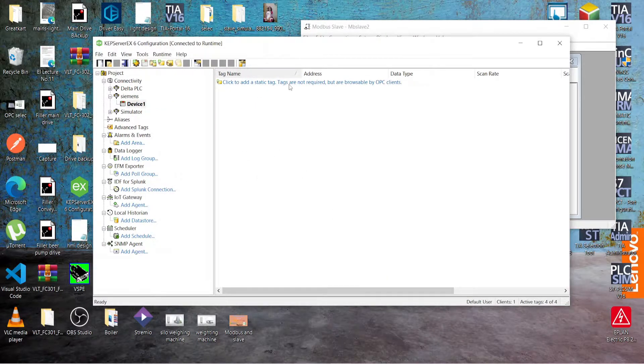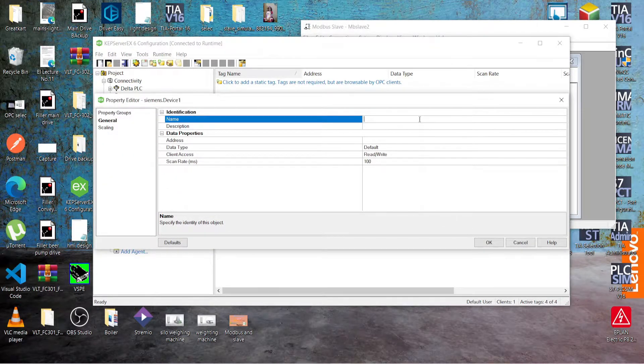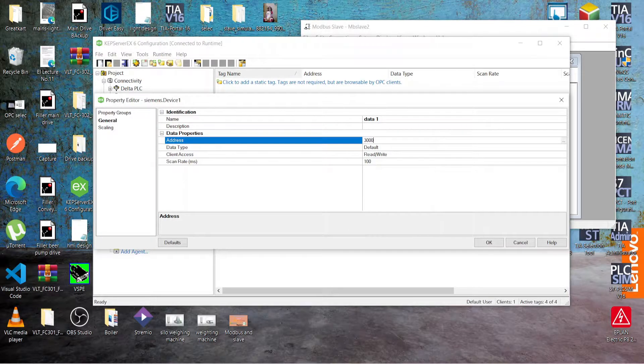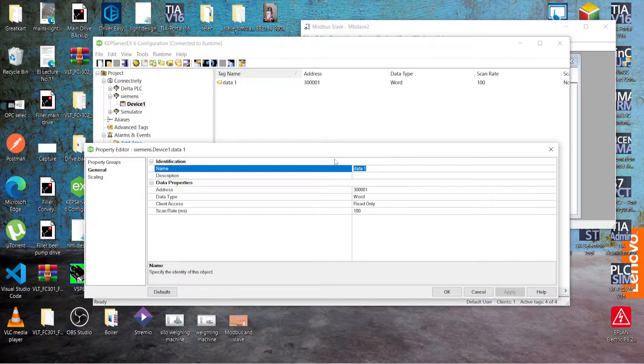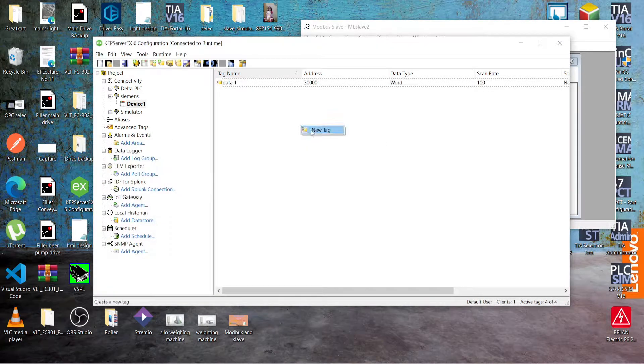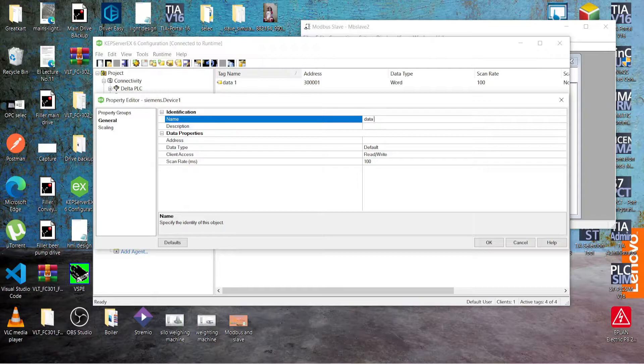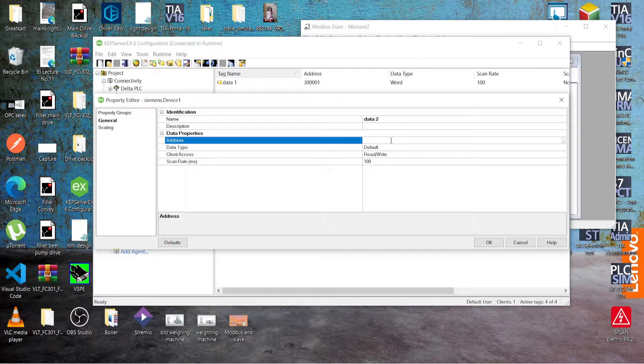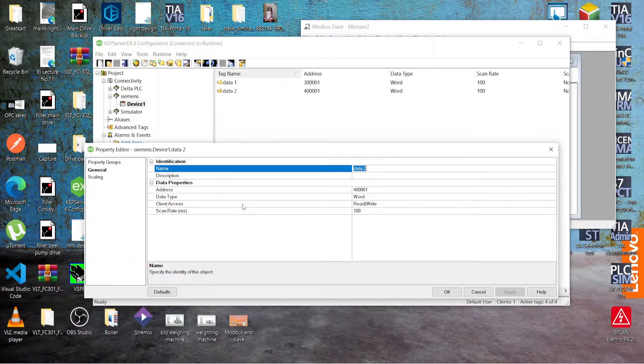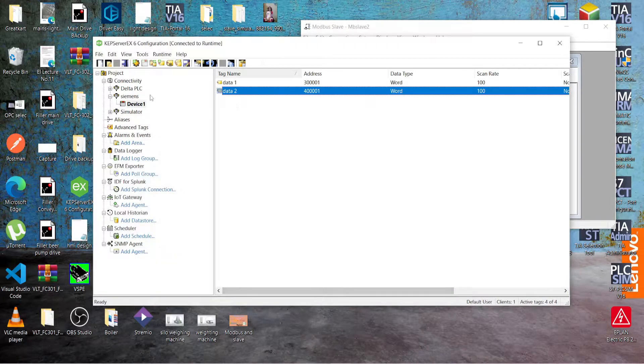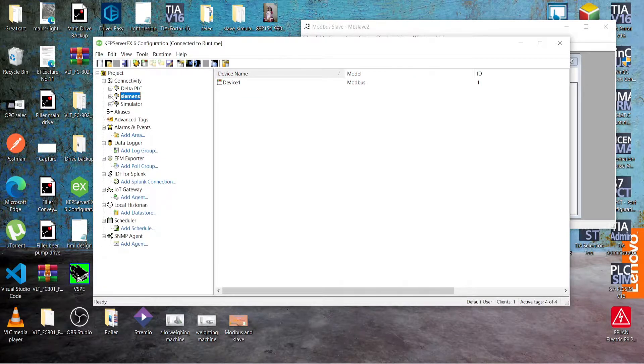Leave every field as it is. Now here you can add tags for values. For the input register address — input registers are read-only memory. For the holding register address, you can read data and even write to this address too. This way you can create a connection in the KEP server.